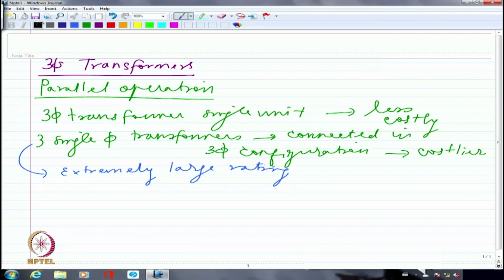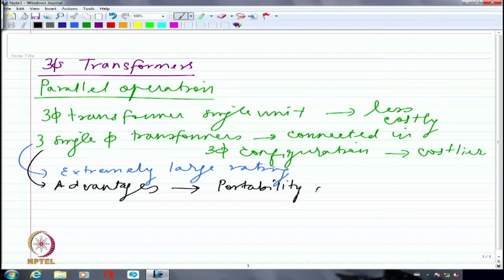So, if I try to write it, I should say advantages of this configuration are portability, flexibility, and one more thing I might mention is, let us say I have three single phase transformers. When I want to store some backup in the inventory, if something goes wrong, I would like to replace maybe one of the single phase units by a good unit. So in that case, I can simply save only a single phase unit. I don't have to save a complete three phase unit.